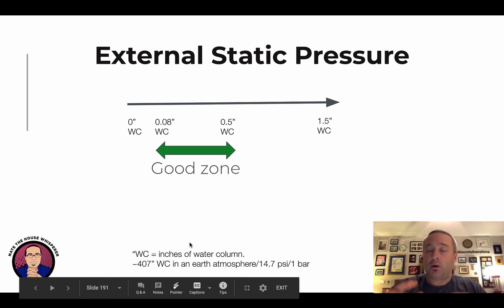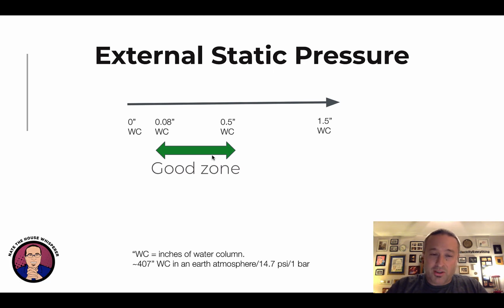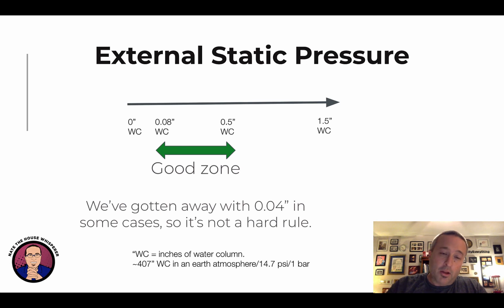And just so you have an idea, Earth atmosphere, how much pressure we're in right now, is 407 inches of water column, which is 14.7 pounds per square inch, or 1 bar. So this isn't a great deal of pressure that we're talking about, but it is, I mean, this is like a very strong wind. It's quite a bit of pressure when you consider the difference that you're normally going to feel. And another important note is we have gotten away with as low as 0.04 inches of static pressure and still had flow, so we still had the velocity pressure happening. So 0.08 isn't a hard rule, but it's a generally accepted rule.